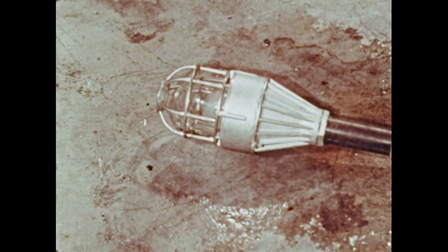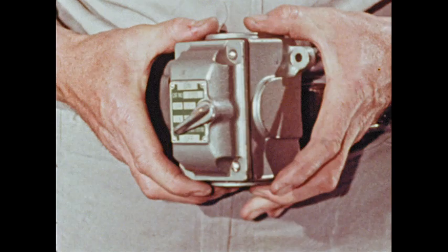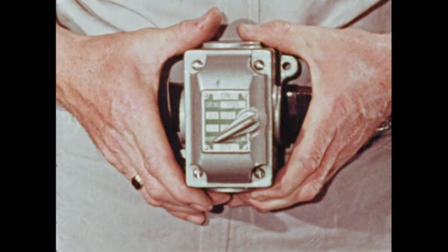Let's spill a little gasoline to illustrate another common source of ignition — the misuse of electricity. When an ordinary electric lamp is used near flammable liquids, there is always a chance that it will be broken accidentally. Even with a wire guard, an ordinary lamp can still be broken. What you really need is an explosion-proof outer globe so that when the light bulb breaks, no fire will result. Electrical arcs and sparks from any source must be avoided, and that's why in flammable liquid areas, special electrical equipment is needed.